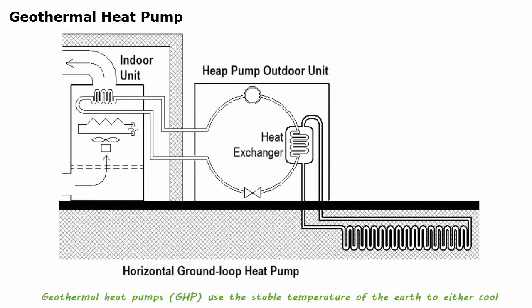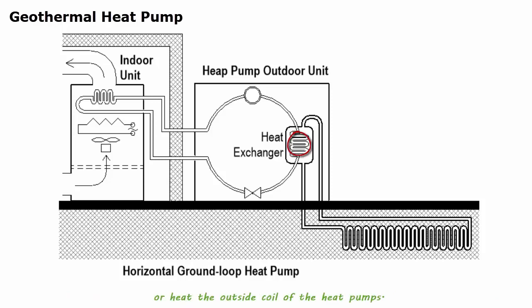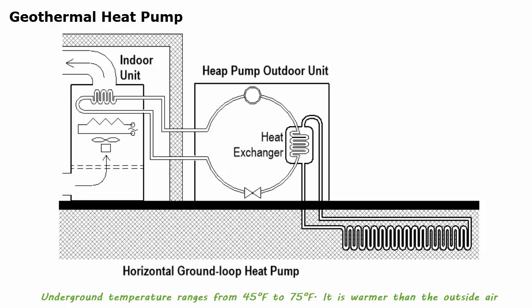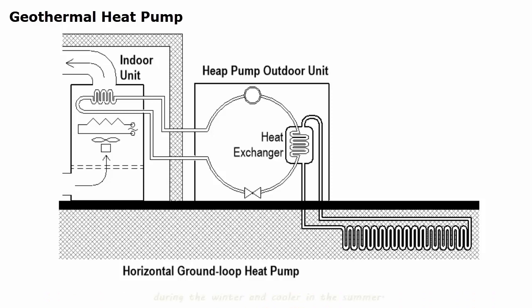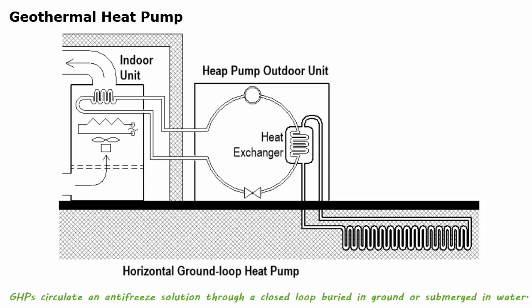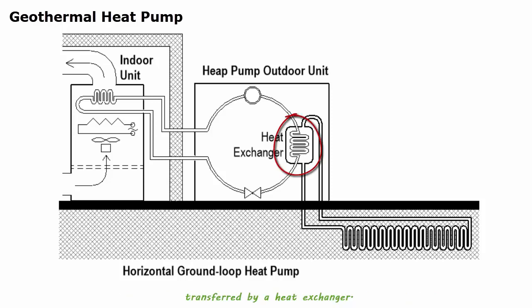Geothermal heat pumps use the stable temperature of the earth to either cool or heat the outside coil of the heat pumps. Underground temperature ranges from 45 degrees to 75 degrees F. It is warmer than the outside air during the winter and cooler in the summer. Geothermal heat pumps circulate an antifreeze solution through a closed loop buried in the ground or submerged in water. The heat between the refrigerant in the heat pump and the antifreeze solution is transferred by a heat exchanger. The loop can be in a horizontal, vertical, or pond lake configuration.